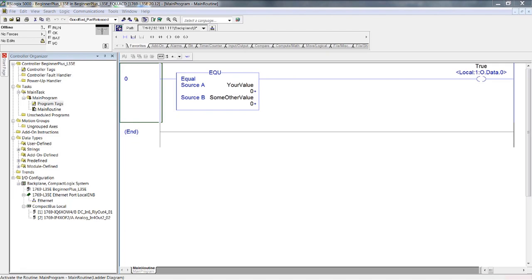A comparison instruction is a mathematical statement or equation that is either true or false, but never both. One equals one is true; one equals zero is false at the digital or binary level. The first instruction we're going to look at is the equal-to instruction. Because this is at a larger value level, you can use it with everything but Boolean — you cannot use Boolean tags for source A and source B. There would be no point using constants for both, though you can use a constant for one of the two.